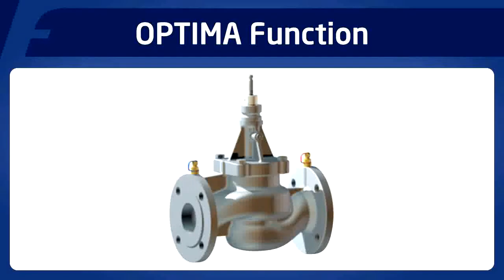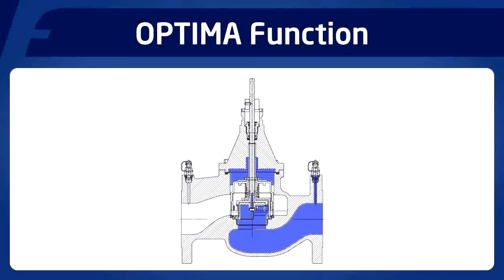So the valve itself, if we take a look at the internals, operates in a way such that the water flows from upstream and enters the bottom of the valve. The upstream pressure then is transmitted through the stem and up above a diaphragm and piston.